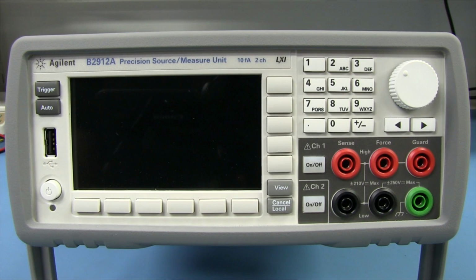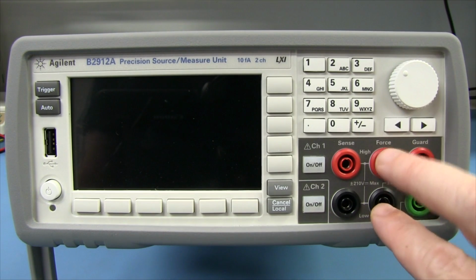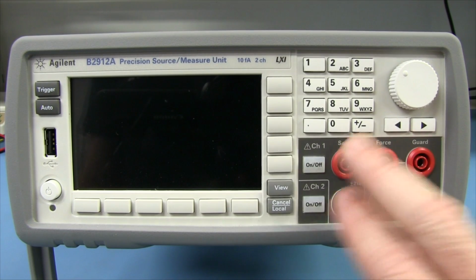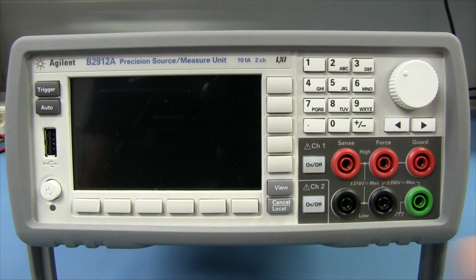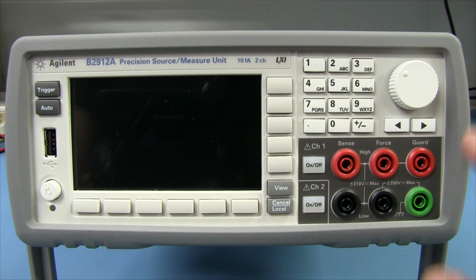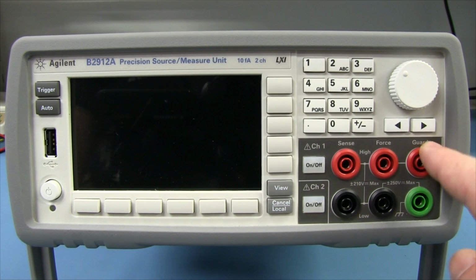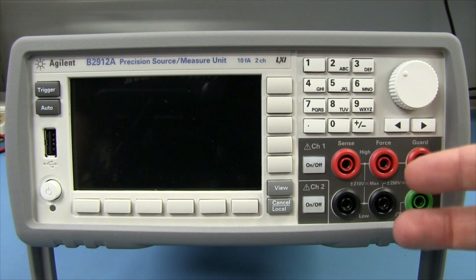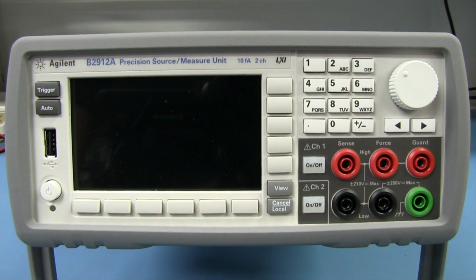So 4 instruments in one, and it can do 2-terminal or 4-terminal measurements as well. And because it goes down to really low currents, we've got things like ground and guard, so you can get triaxial test cables and things like that, which we might go into in another video, actually using this thing in a real world scenario if you want to take a look at it.